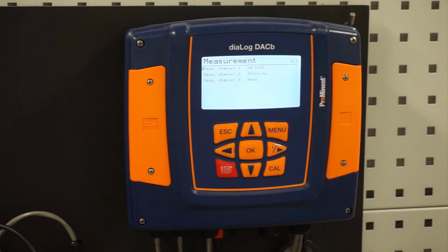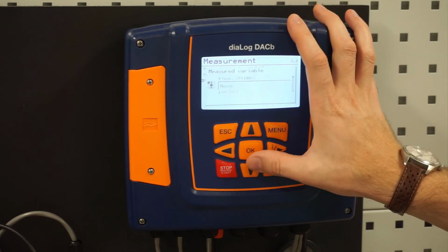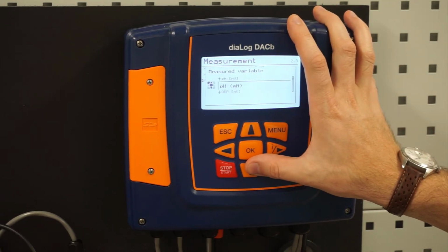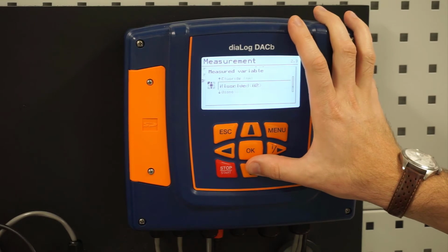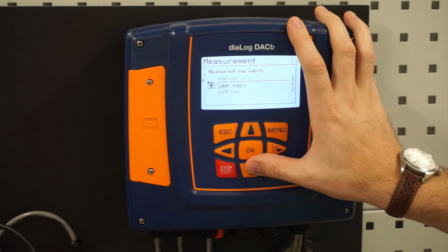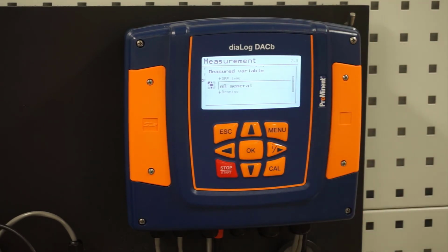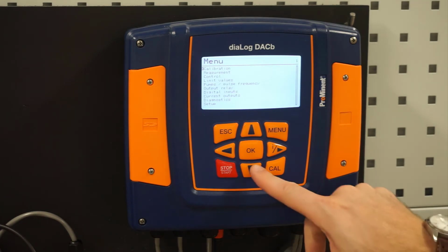We also have our third channel. In this case, we're not using it. If you were to go into it, you can see what options you have available for it. So chlorine, bromine, chlorine dioxide, chlorite, fluoride, dissolved oxygen, ozone, peracetic acid, hydrogen peroxide, conductivity. There's numerous options that we could add on to this controller because it is currently open. We're going to back out. We are done with our measurement screen.